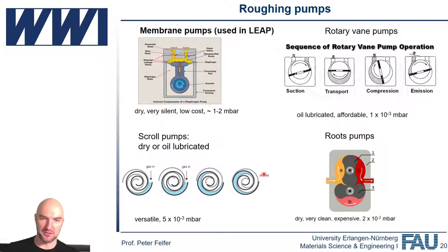If you want to get to the same level, there's also scroll pumps, and they're getting increasingly more popular, where you have two scrolls, usually made from Teflon, that move in an eccentric way relative to one another, and compress any gas from the inside this way and push it out in the middle of the pump.